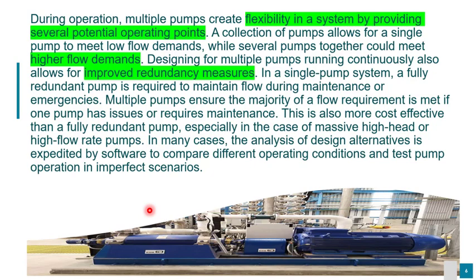In a single pump system, a fully redundant pump is required to maintain flow during maintenance or emergencies. Multiple pumps ensure the majority of a flow requirement is met. If one pump has issues that require maintenance, this is also more cost effective than a fully redundant pump, especially in the case of massive high head or high flow rate pumps. In many cases, the analysis of design alternatives is expedited by software to compare different operation conditions and test pump operation in imperfect scenarios.